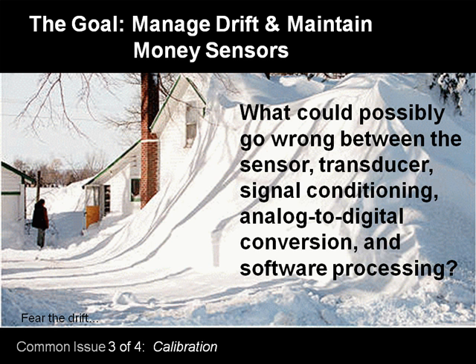You also have a transducer, which takes a form of energy like pressure or temperature and converts it into a different type of signal. You have that on your diaphragm pushing on it, and it's going across the resistor. Things wear. Then you have signal conditioning, where you're taking an analog signal coming in and converting it over to a different type of signal. And then you have the software that processes the whole thing and puts up the number that you see in front of you. So there's a lot going on behind the scenes when you look at your building system and you see that the outside air temperature is 30 degrees outside. A lot went into bringing that 30 up in front of your eyes to see, and a lot can go wrong. A lot of guys say, oh, that came from the factory, and it was calibrated at the factory. And then it rode a train, then a UPS truck, and then it got in the back of the guy's service truck.